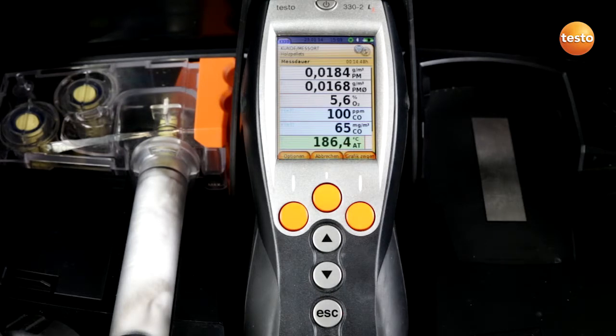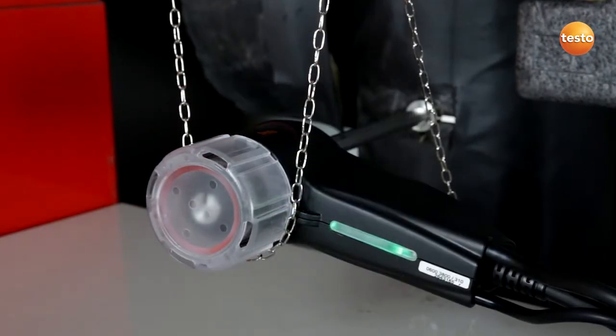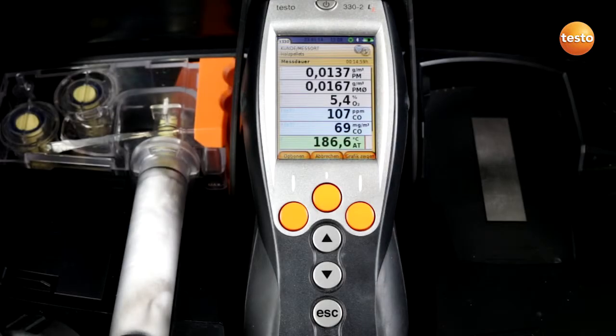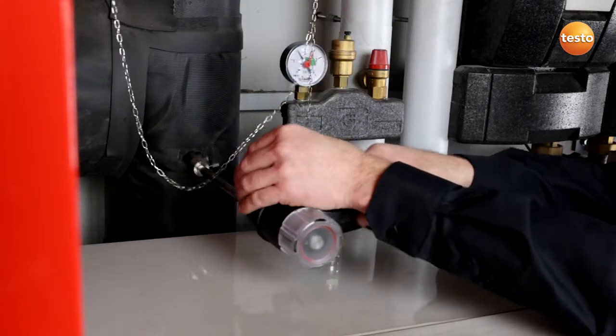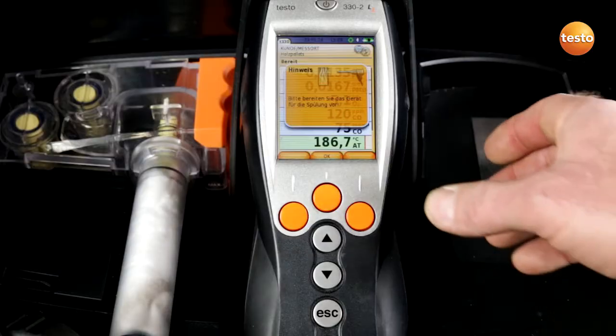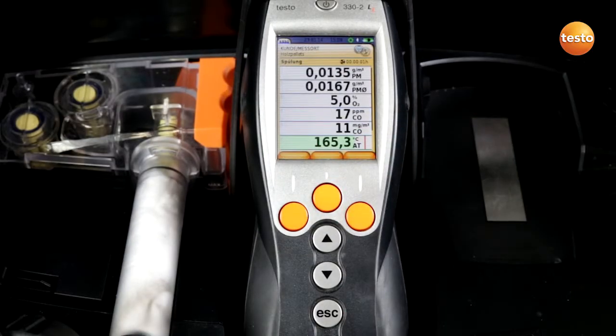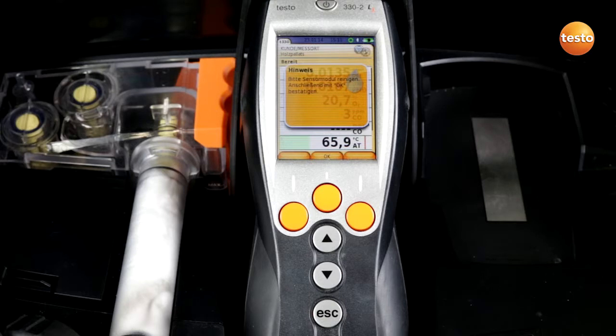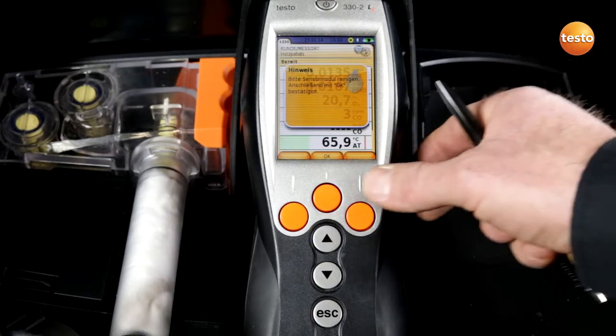The measurement duration of 15 minutes is now nearly over. After 15 minutes, the measuring instrument automatically switches off. I'm given the instruction to remove the flue gas probe from the gas flue and to prepare it for flushing. I confirm this with OK. Flushing has begun and will take about 2 minutes. At the end of the flushing procedure, it shows me the total values over the 15-minute measurement. The flushing procedure is now finished. I confirm this with OK.